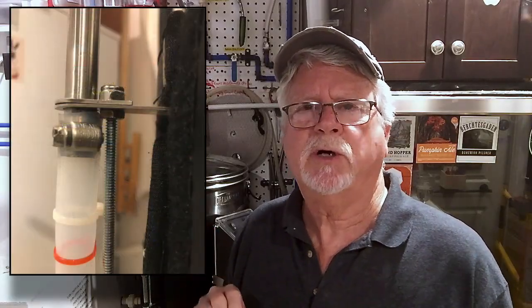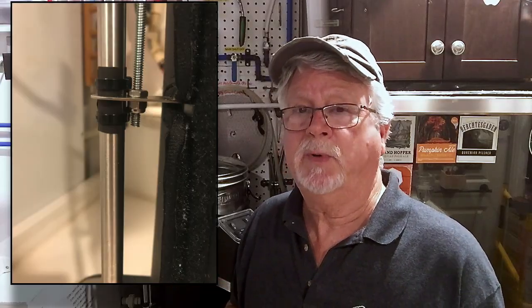Now, taking out a section of the pipe will weaken the rigidity of the pipe, so I installed a threaded rod between the two discharge pipe brackets and secured the rod with lock nuts on both sides of the brackets. Lastly, I filled the boiler with water and I marked off various levels with different colored tie wraps.